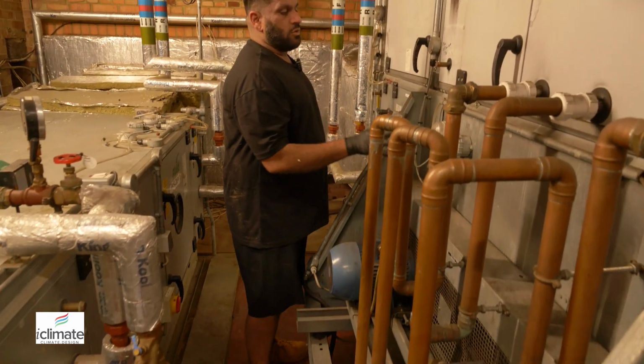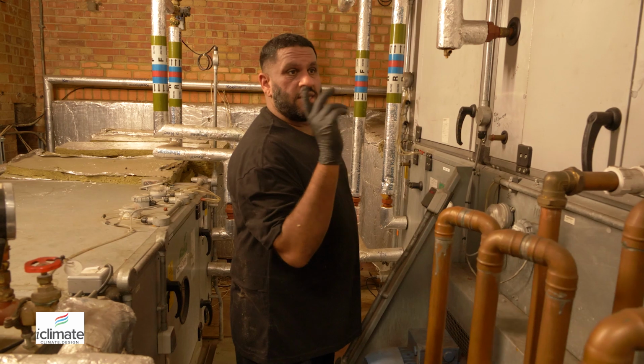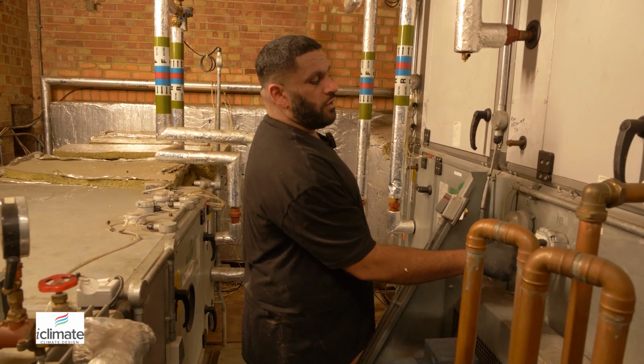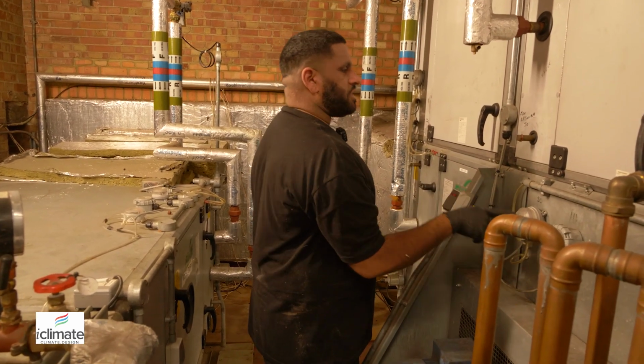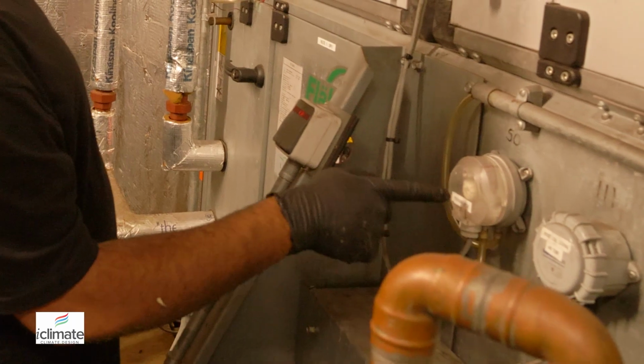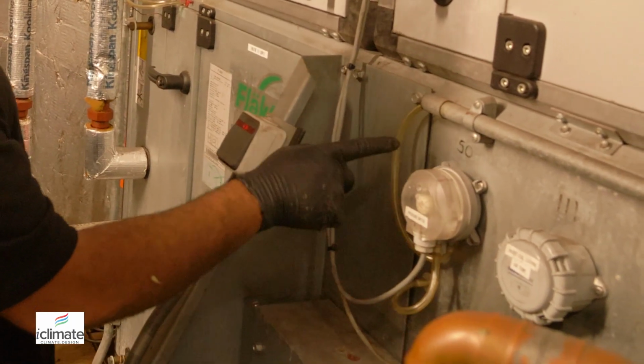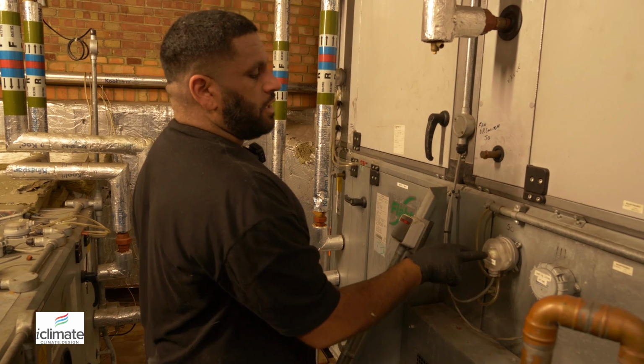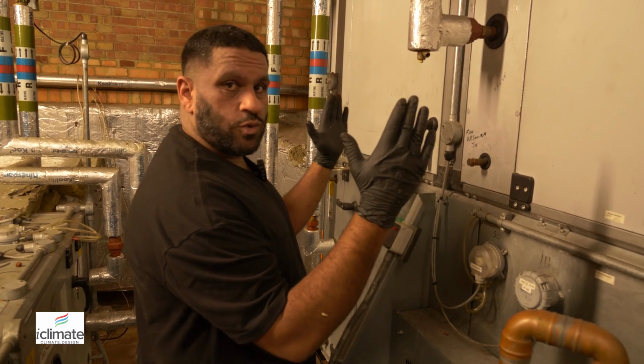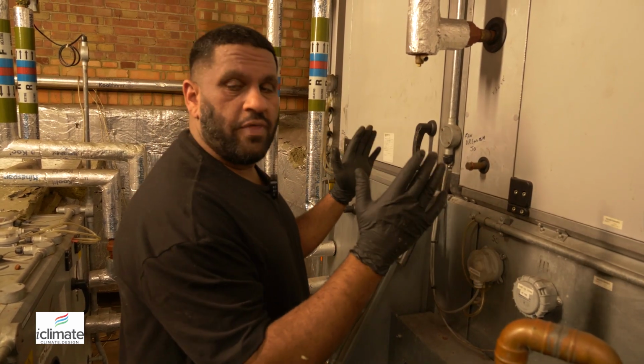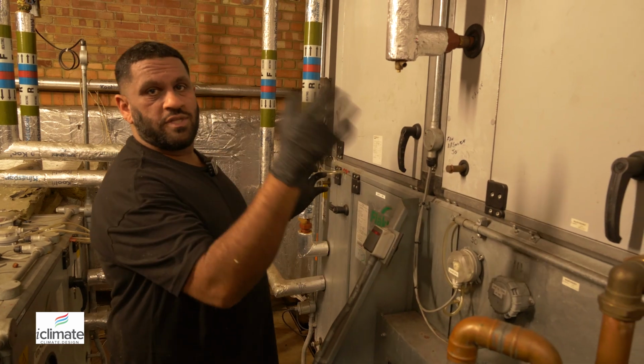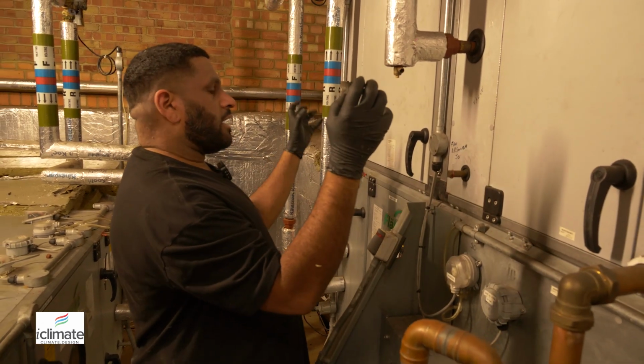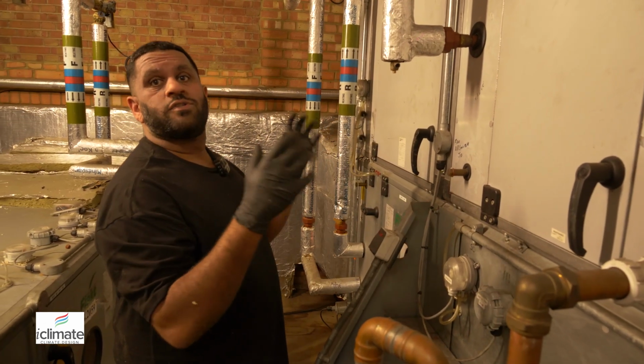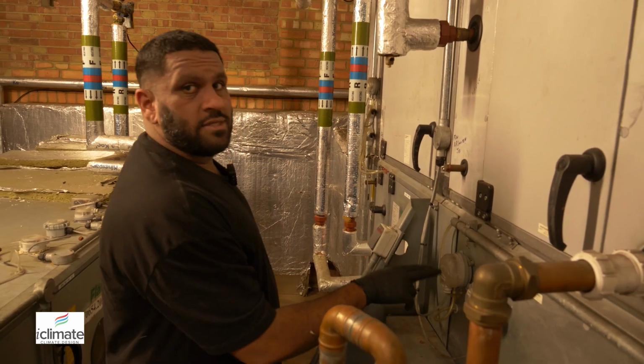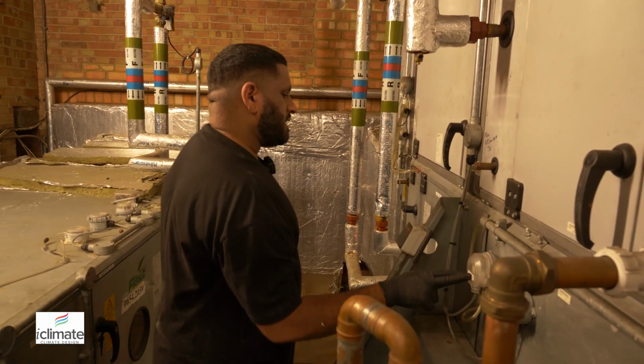Air handling units always have lots of sensors, and these are connected to the BMS system. We've got a frost coil temperature sensor and a pressure switch. These you guys might see a lot. They are pressure differential switches. They're normally across a filter. So this gives you an indication of when there's a great pressure differential across a filter. That means one thing, the filter is blocked. We've got a pressure on this side that has too much of a delta compared to the pressure that's here. And that can mean a restriction, a blocked filter. That's the main purpose of pressure differential devices.